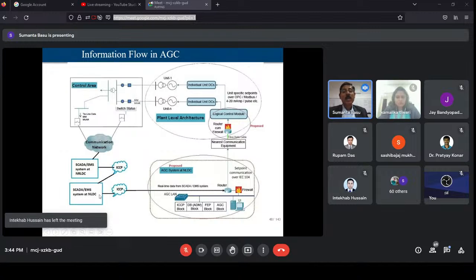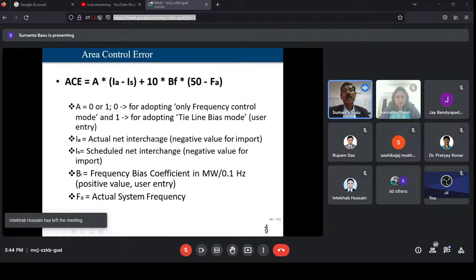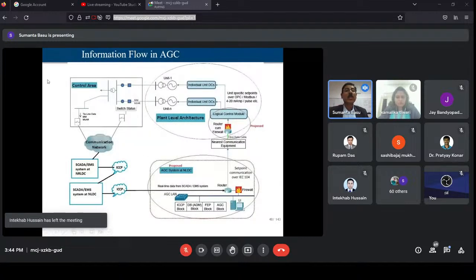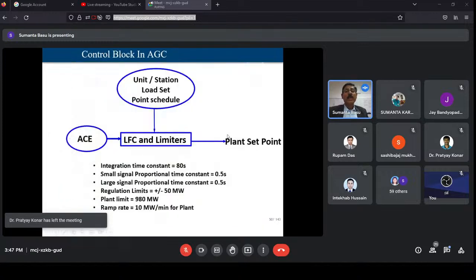So NLDC, National Load Dispatch Center, through router and firewall gives the plant level the actual generation requirement. That goes to the DCS, that goes to the generating station, which is catering power to that particular control area. So this is the scheme of how AGC can stabilize the power grid. This is how the area control error I have shown also. The same thing has been implemented in this slide, how the area control error is controlled and calculated. Based on that setup, we have found that the integration time constant is around 80 seconds under that instability event on the grid.